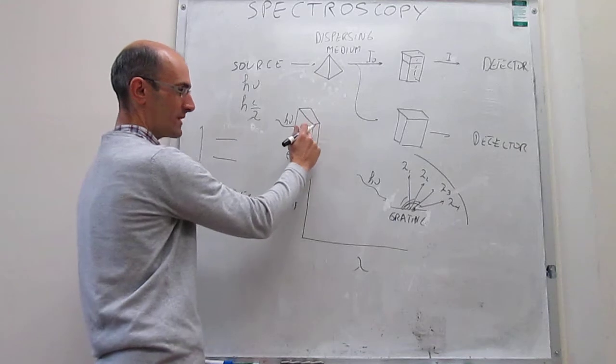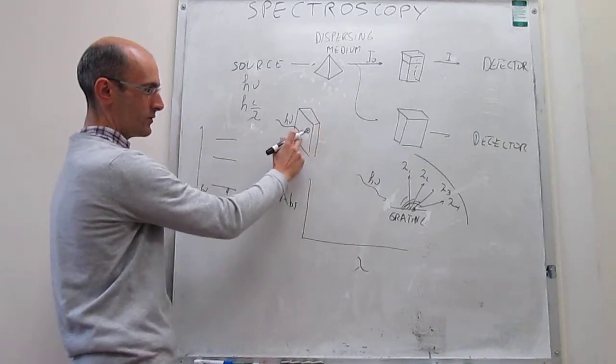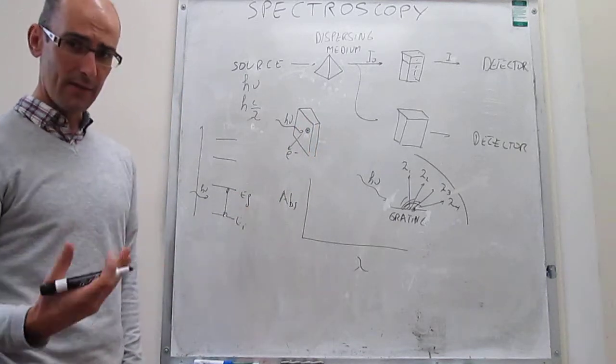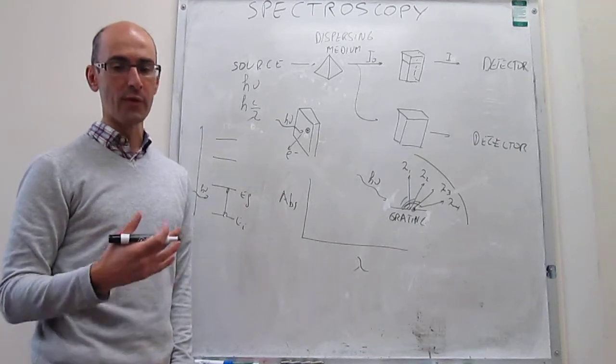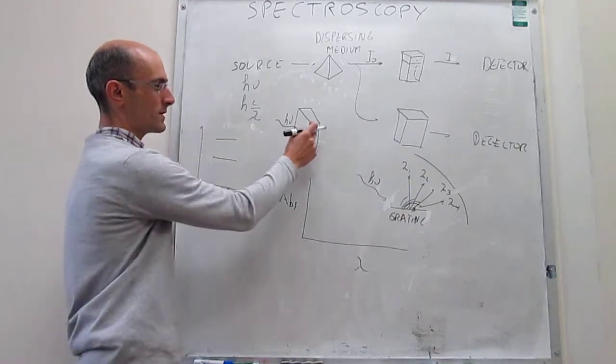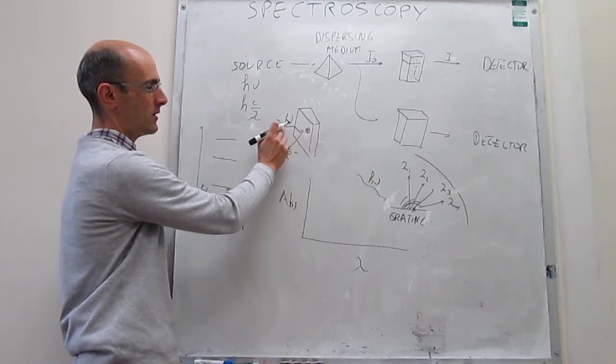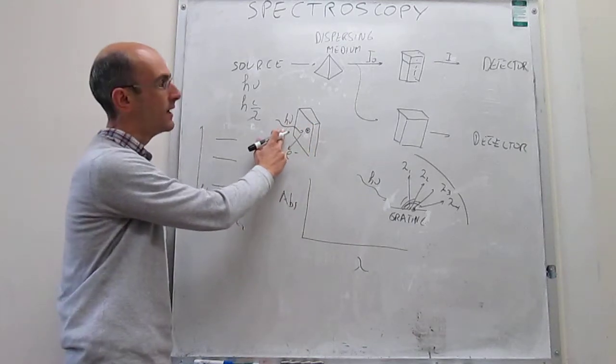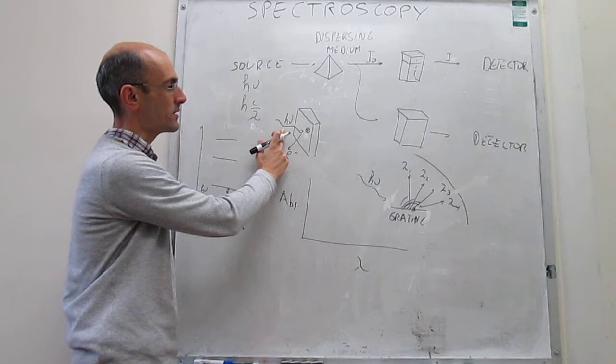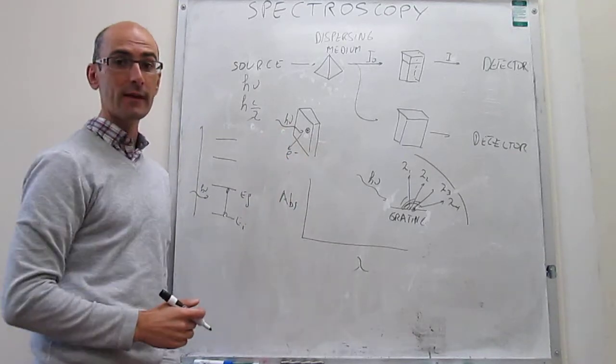And it turns out that you can actually measure the current due to those positive holes, and that is really proportional to the number of photons that have arrived. So by measuring this current generated by the positive holes, you can detect how many photons have arrived at the detector, and from there you can calculate the absorbance.